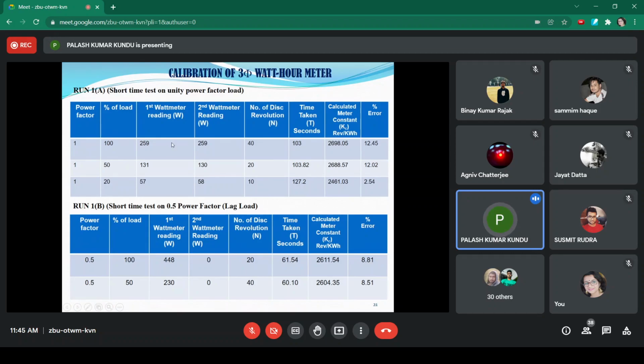But if the power factor is reduced further to 0.5, then the number of disc revolutions to set should be increased, not reduced, to 20, 40, like that, so that sufficient time is allowed: 61.54 and 60.10 seconds. When the power factor of 0.5 is set, under the short time test, the error in meter constant is 8.81 and 8.51. There is a scientific reason why, under reduced power factor, the error will be small: the speed of the disc will fall under reduced power factor. The more the speed of the disc, the more the chance of error in the meter constant.